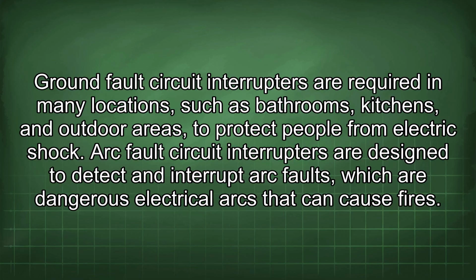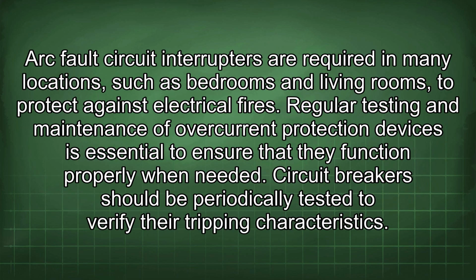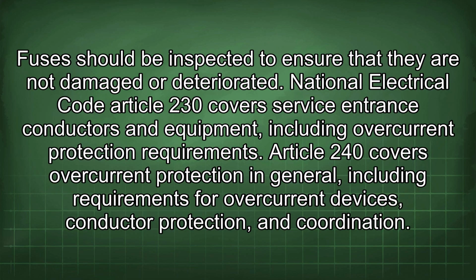electric shock. Arc fault circuit interrupters are designed to detect and interrupt arc faults, which are dangerous electrical arcs that can cause fires. Arc fault circuit interrupters are required in many locations, such as bedrooms and living rooms, to protect against electrical fires. Regular testing and maintenance of overcurrent protection devices is essential to ensure that they function properly when needed. Circuit breakers should be periodically tested to verify their tripping characteristics. Fuses should be inspected to ensure that they are not damaged or deteriorated.